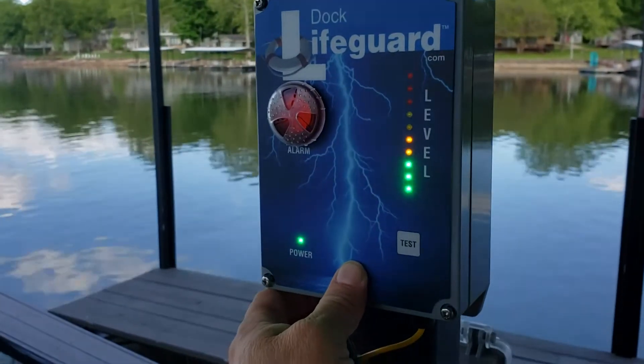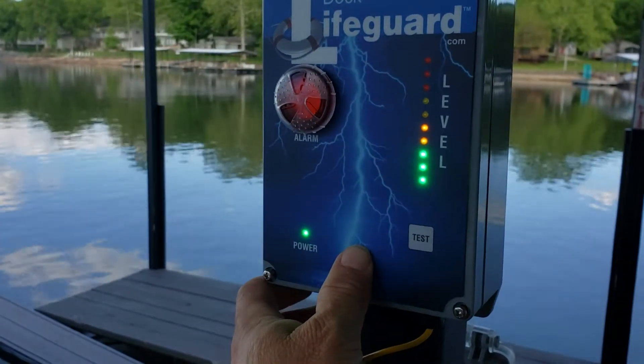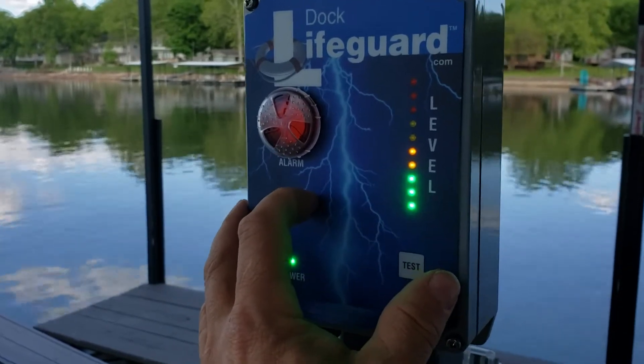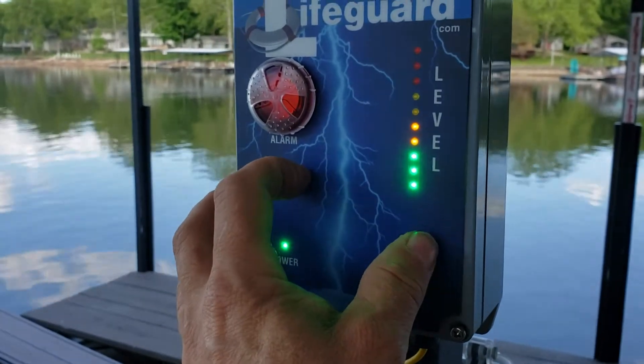The factory default is zero volts. In this scenario, the dip switches are set to 0.25 volts, so we're seeing about 1.25 volts in the water. We want to set our baseline to alarm at maybe one volt over that 1.25 volt baseline.